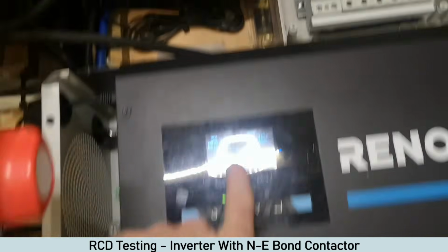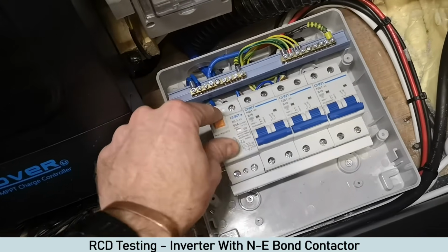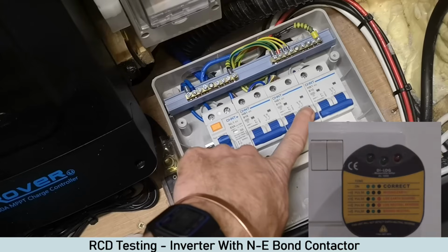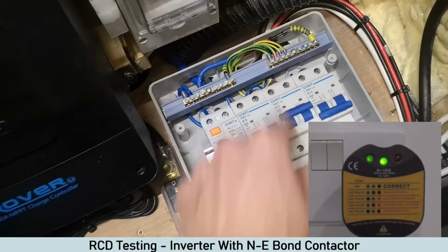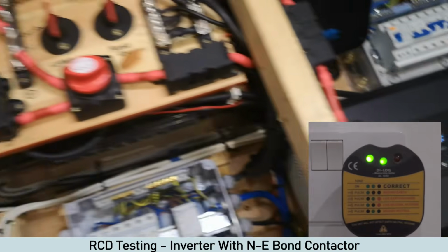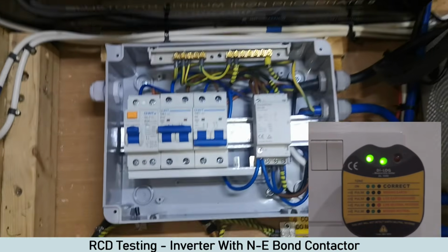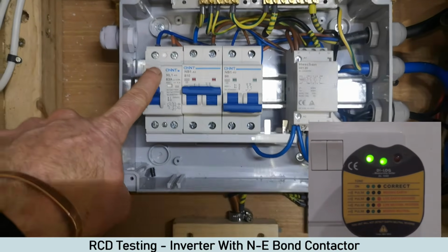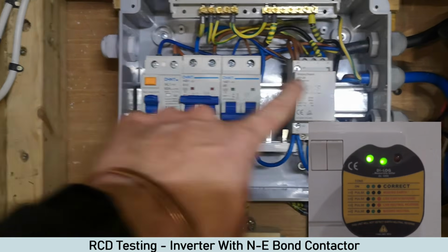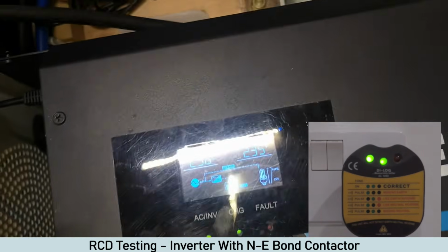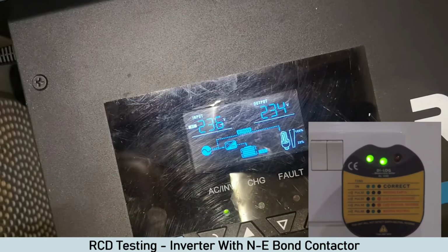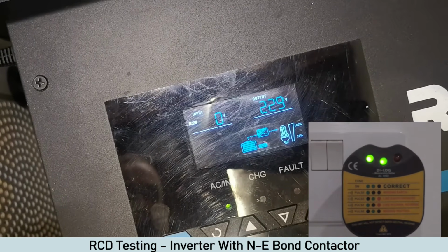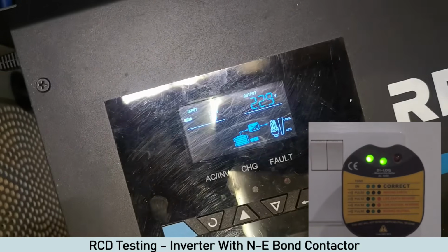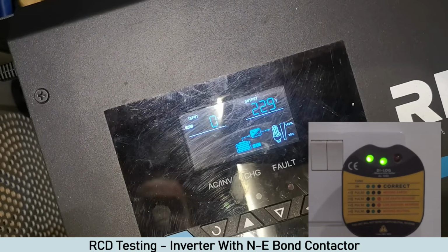Okay, so hookup's on, inverter's on bypass, RCD is working. I'll switch that on, which will turn the noisy socket tester on. So you can see there that it's on. So what I'll do now, I'll create a scenario where the mains turns off, this will turn off, and this will turn into inverter. So that's immediate, and you can see how fast the socket tester, there was no interruption at all. So it's now on inverter.